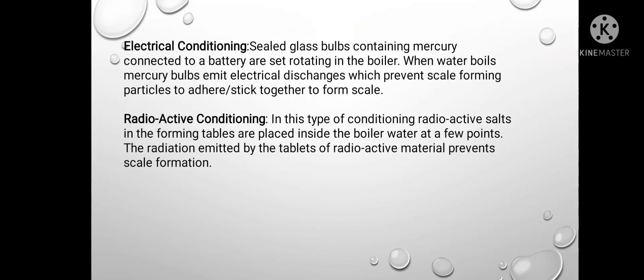Electrical conditioning — sealed glass bulbs containing mercury connected to a battery are set rotating in the boiler. When water boils, the mercury bulb emits an electrical discharge which prevents scale-forming particles from adhering or sticking together to form a scale. Fifth, radioactive conditioning — in this type of conditioning, radioactive salts in the form of tablets are placed inside the boiler water at a few points. The radiation emitted by the tablets of radioactive material prevents scale formation.